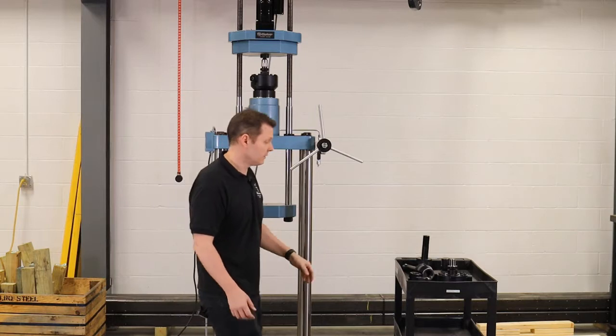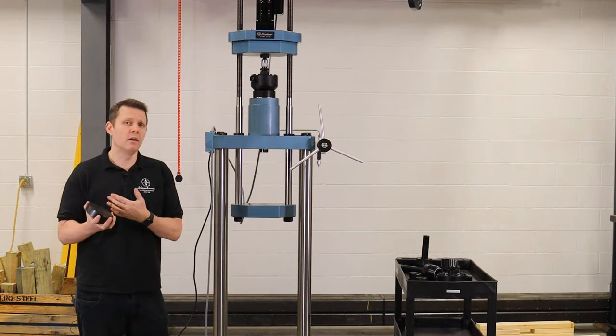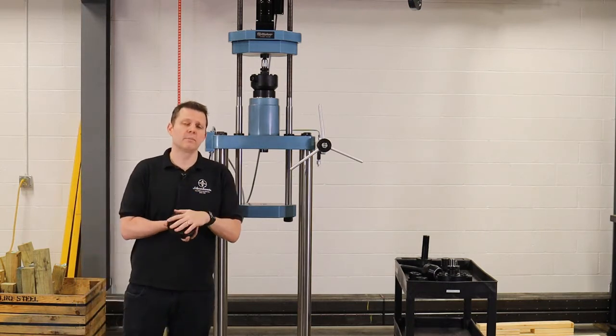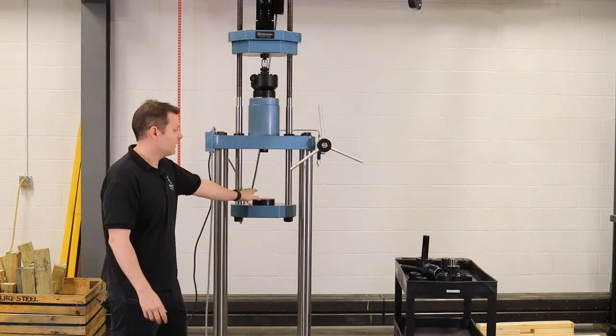The first thing we're going to do is, of course, Morehouse, we sell all of these adapters. We have this compression plate that slides right in on the lower yoke, fits right in, has a hole for centering for our load cell.